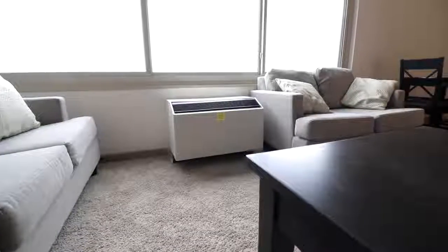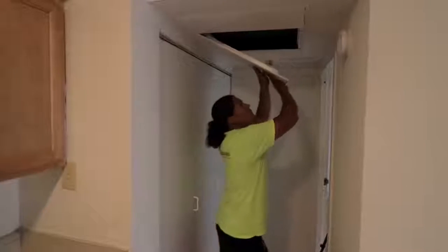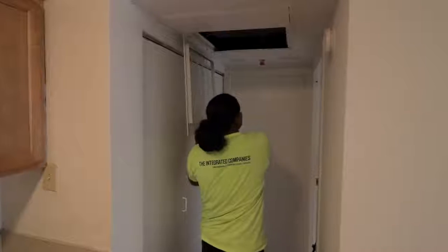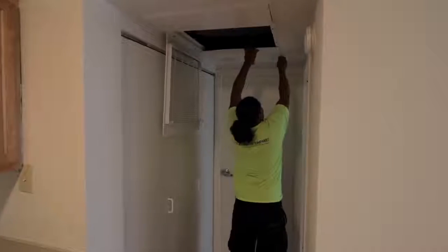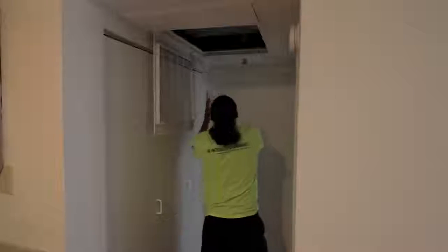So we looked at this building at all our different options, and what we settled on was a VRF system. There's low ceiling heights, and it's a tall building, 22 stories, so you're looking in the range of about 180 to 200 feet of building. So we looked at VRF, we looked at the efficiency, and it turned out to be a good solution.